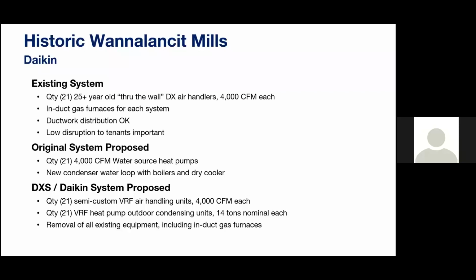So the largest standard VRF indoor unit is an 8-ton horizontal ducted unit, which is limited to around an inch of static, which Jason mentioned. So what we needed here for each zone was around 12 to 14 tons, which was outside of the standard VRF indoor unit range. And we also needed around 2 to 3 inches of static. So again, long duct runs. And then we also wanted to reuse some of the existing ductwork.